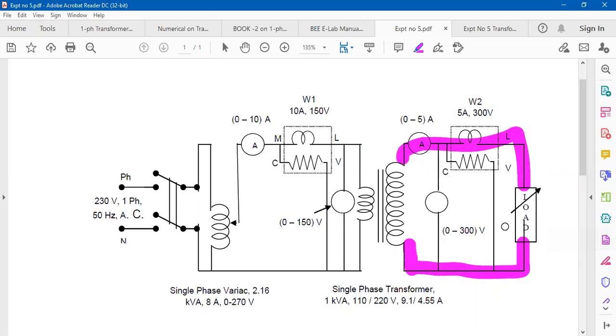A lamp load — tungsten filament incandescent lamps — is used as a purely resistive load. For a purely resistive load, the power factor is unity, meaning the total voltage across the load and total current through it are in phase. Lamps are connected in parallel: initially 2 lamps, then 4, 6, 8, 10, and so on. As load increases, primary and secondary side voltage, current, and power are recorded to calculate voltage regulation and efficiency.